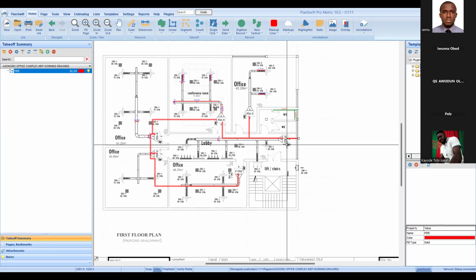And let's not forget that we didn't know the distance to where our outdoor unit will be. Like the picture I showed you, we didn't know where it will be. But let's allow an extra 6 meters away from the building, to be on the safer side. That's 54 plus 6, a total length of 60 meters of cable. Now, in this 60 meters, if you are told that it is 1 core by 4 mm, it shows that 60 meters times 4 runs makes 240 meters. But if the cable you are using is 4 core by 4 mm, it shows that in one cable you'll see 4 cables joined together as one. Are you getting? Now, in this case, we have 60 meters of 4 core by 6 mm cable. Now, we've already calculated for cable.